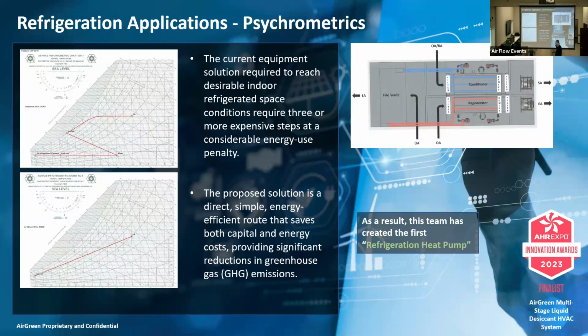And then the interesting stuff that we've been working on for the past year is using refrigerants to chill the desiccant and looking at cold storage applications where you need outside air, you need make-up air systems. You need to make sure that the dew point is not met. Because if you start to get dew in some of those places, then all of a sudden they have to call the FDA in, you have cleaning procedures and downtime and all of that. So it's pretty important. And from a safety point of view as well.